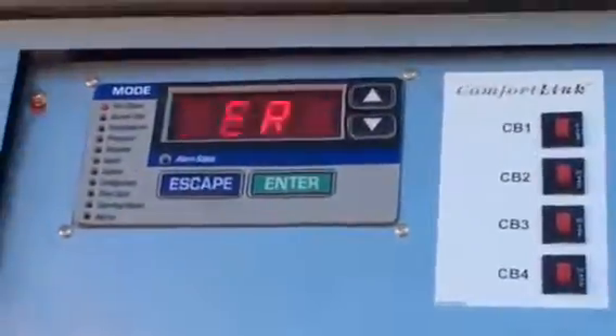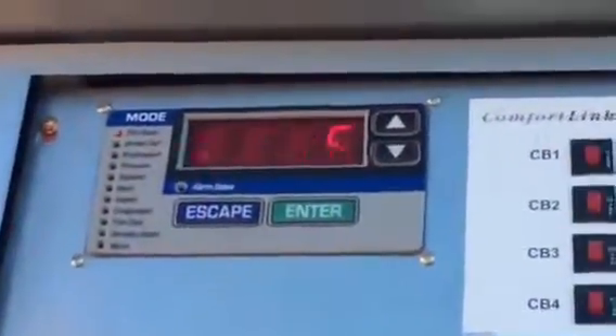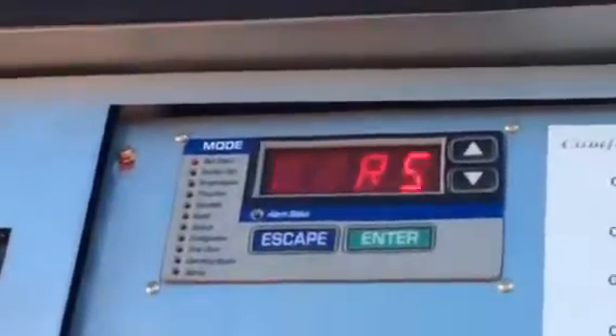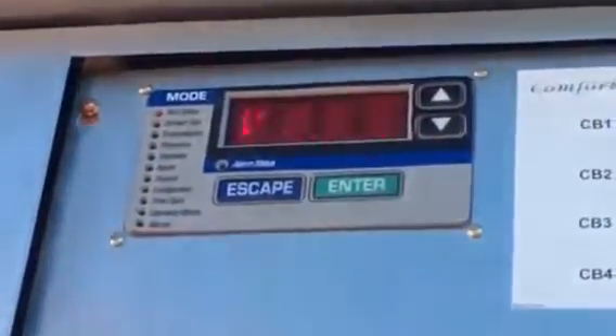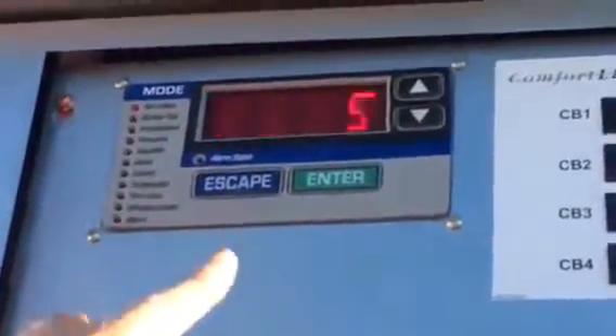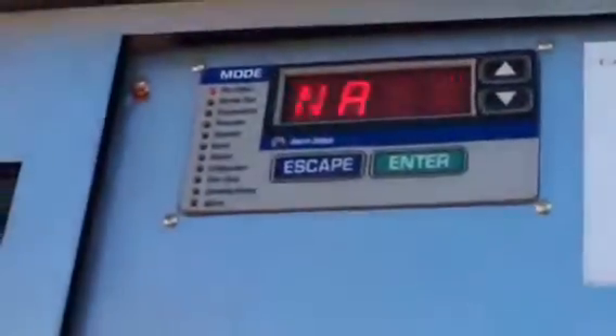We missed looking for. The other thing through run status, sometimes if troubleshooting things come up or if you call my guys in tech support, they know more than I do, thank God, right? Sometimes I'm going to ask for software versions. Within run status, if I scroll all the way down to version, it gives me a choice of main baseboard, ECB1, ECB2, the marquee itself, navigator. If I was plugged in, it would give me that information. So a lot of times what I want to know is main baseboard. If I hit enter, enter and escape, pardon me.